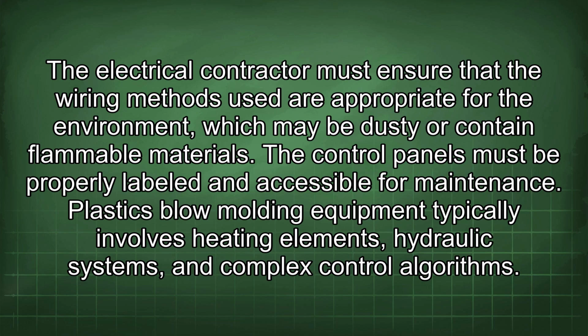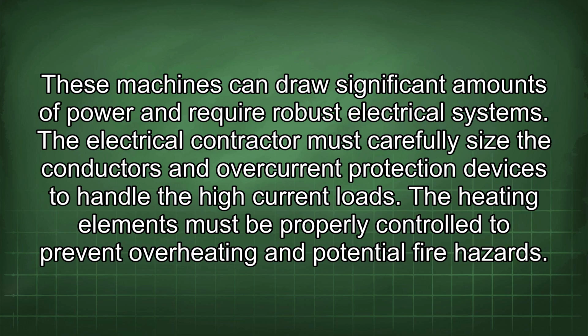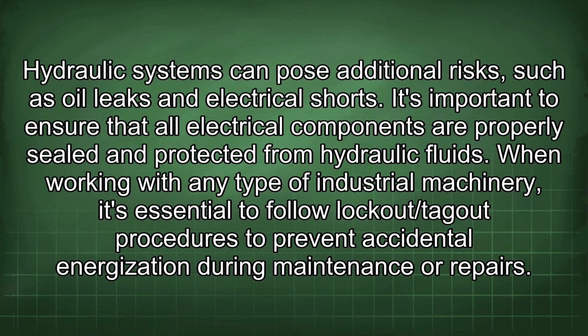Plastics blow molding equipment typically involves heating elements, hydraulic systems, and complex control algorithms. These machines can draw significant amounts of power and require robust electrical systems. The electrical contractor must carefully size the conductors and overcurrent protection devices to handle the high current loads. The heating elements must be properly controlled to prevent overheating and potential fire hazards. Hydraulic systems can pose additional risks such as oil leaks and electrical shorts. It's important to ensure that all electrical components are properly sealed and protected from hydraulic fluids.